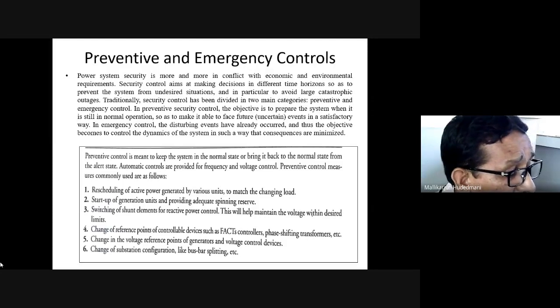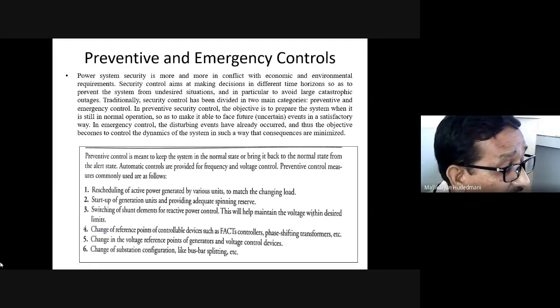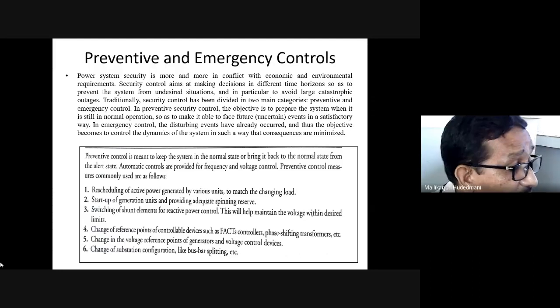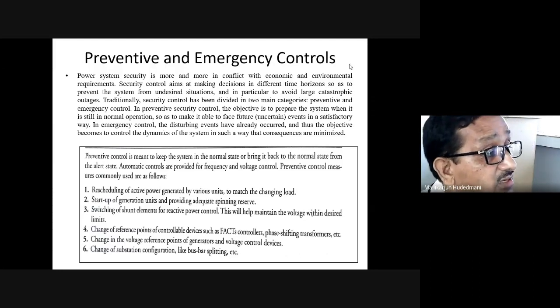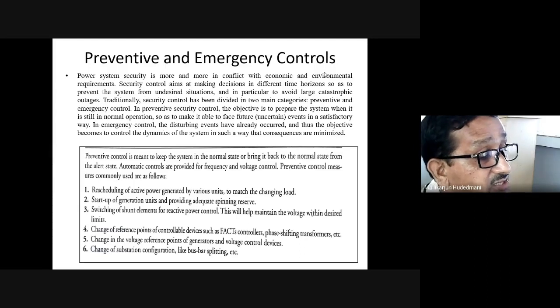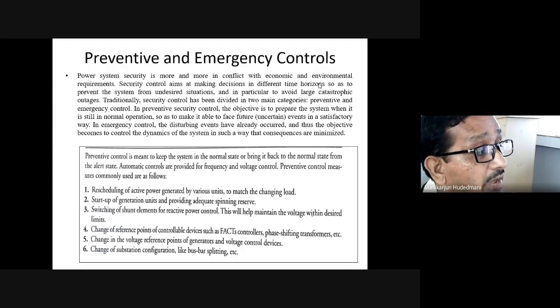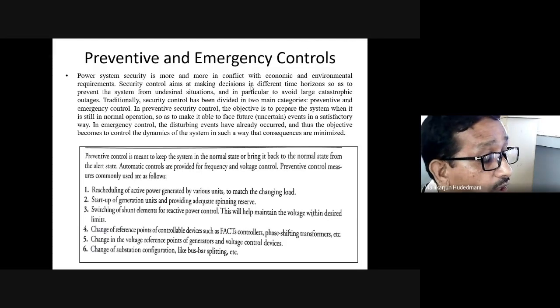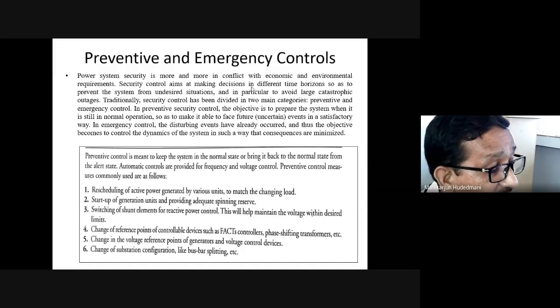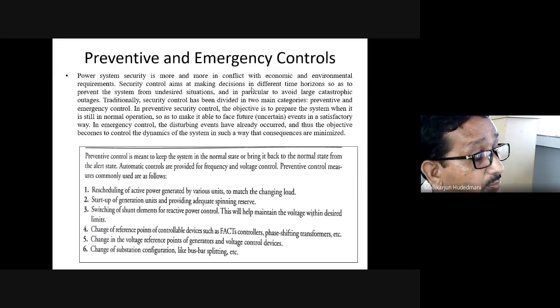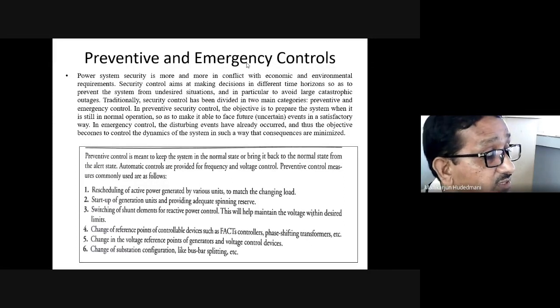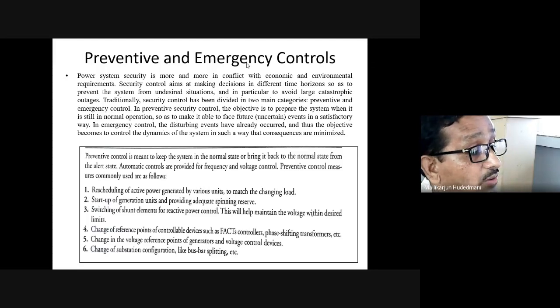Transformers are fully loaded, tap settings have reached the maximum, and transmission lines are running over because we have not taken proper distribution, rescheduling, reorganizing, or curtailment of load. Something has not been planned. Suddenly, the system has entered an emergency. Likely, any further contingent variation is sure to damage the system. In which case, emergency control should control the system slowly, in steps, back to at least an operable state. That is how these are.